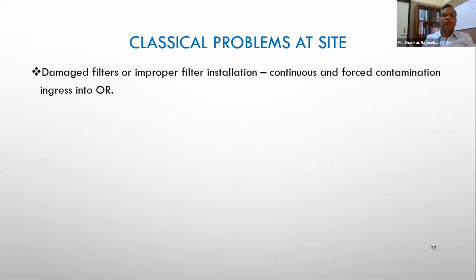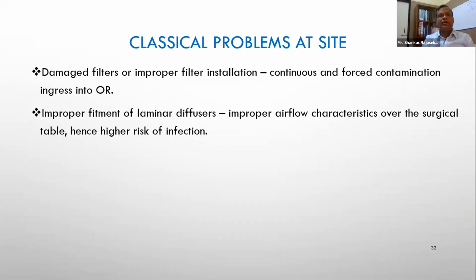Damaged filters or improper filter installation. Improper fitment of laminar flow diffusers. This is the most important thing. The reason being, as we said, if the velocity uniformity is affected, then the laminarity is lost. If the laminarity is lost, it loses the capability to transport the contaminant away. So if you don't fit the laminar diffusers properly and in a leak-free manner, there is a difference in velocity, because of which the very purpose of providing a laminar diffuser is lost.